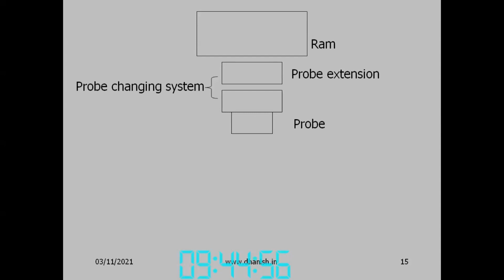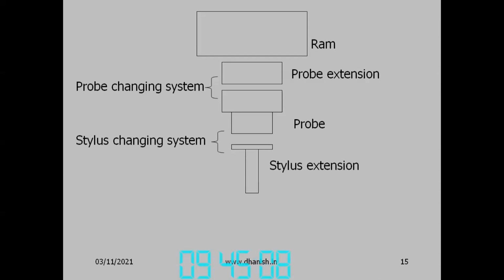The probe actually controls the measuring force, the force it uses to contact the workpiece. So you can apply different forces by choosing different probes. Then the stylus is fixed onto the probe. The stylus is the part which contacts the workpiece. You can choose different diameter styluses. That is the stylus tip on a stylus shaft. In between, you can extend the length of the stylus by having stylus extensions. The whole thing can be fixed onto a probe, and the stylus part can be changed.